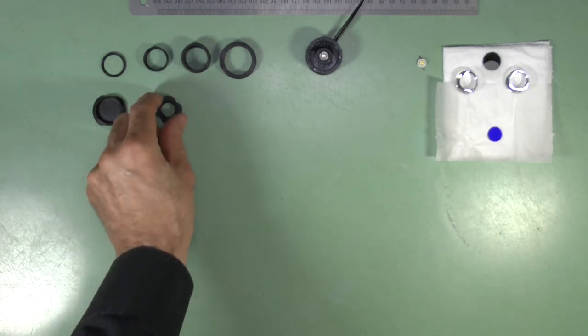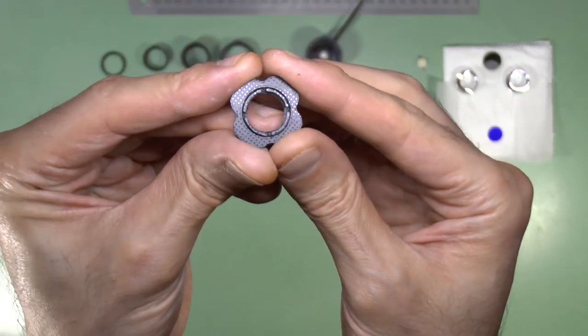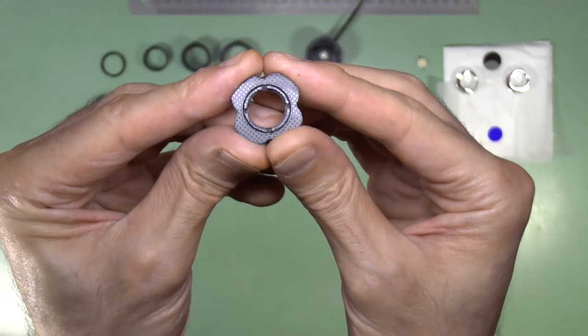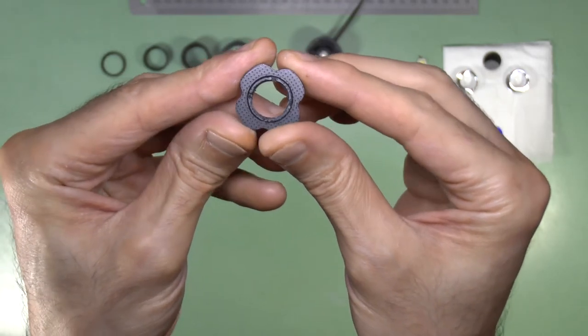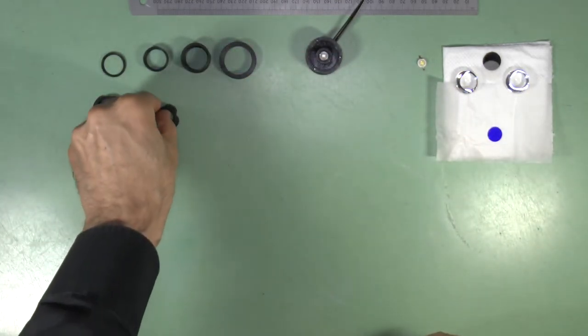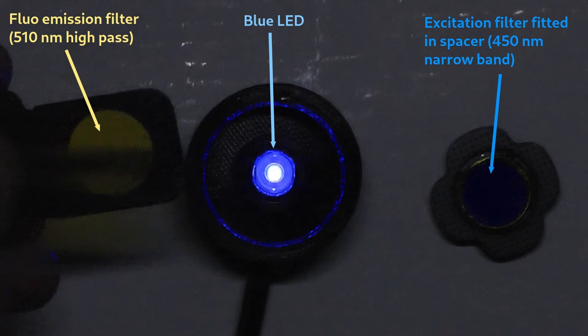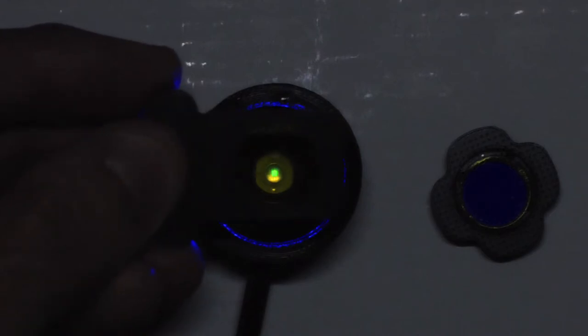In regards to fluorescence, note that this spacer has a specially designed flexible rim receptacle well in its top surface for accepting a filter 14 millimeters in diameter by up to one millimeter thick. In this case we'll be using a 450 nanometer narrow bandpass excitation filter. This is needed because the blue LED, despite having a stated output wavelength range of 460 to 465 nanometers, also has a significant amount of yellow green residual emission which gets through the 510 nanometer emission filter used for fluorescence fluorescence microscopy. This results in high background brightness which makes this LED unsuitable to detect faint fluorescent signals if used without a filter.